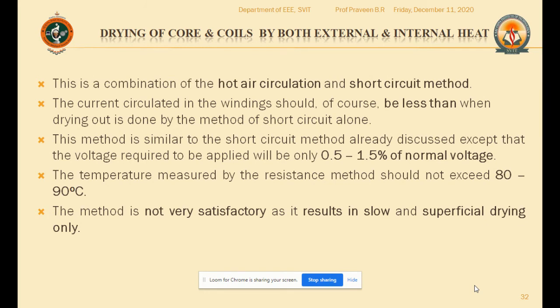In this, we use both the hot air circulation method and the short circuit method. The currents circulated in the windings should be lesser than when drying out is done by the short circuit method alone. This method is similar to the short circuit method we have already discussed with the oil, except that the voltage required to be applied will be around 0.5 to 1.5% of the normal voltage.